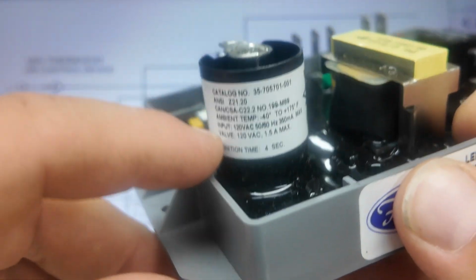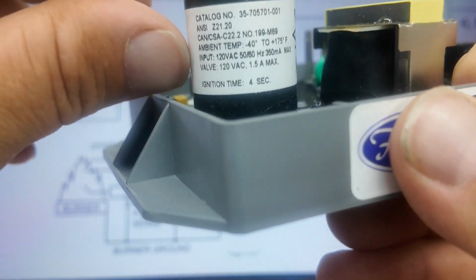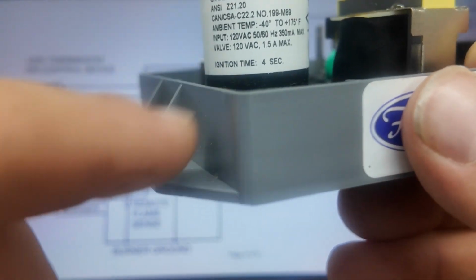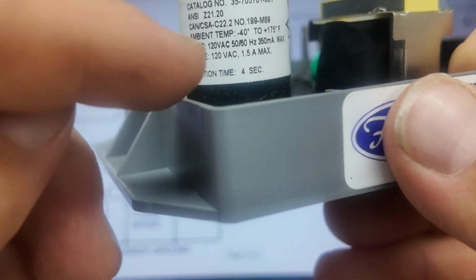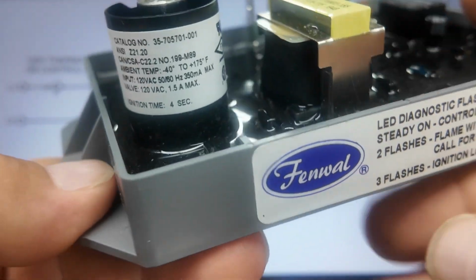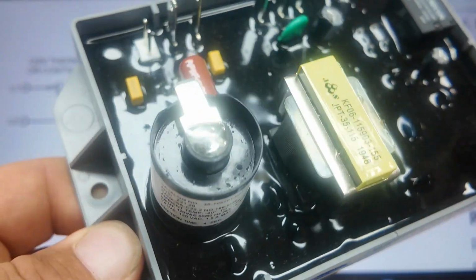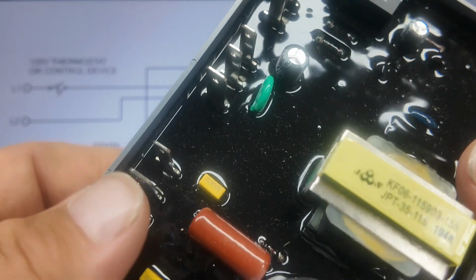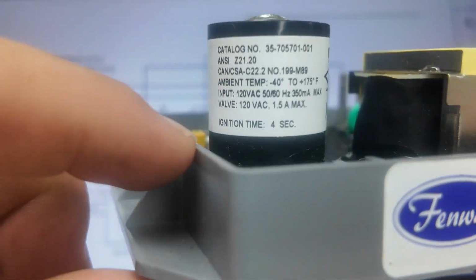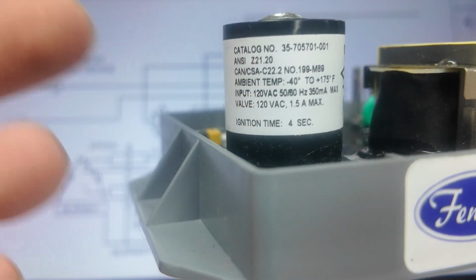Now you'll see on the ignition coil right here, it says ignition time 4 seconds. So this has a 4-second delay from when you put power to it. There's a 4-second purge time. Here it's called ignition time, but I would call it the purge time.